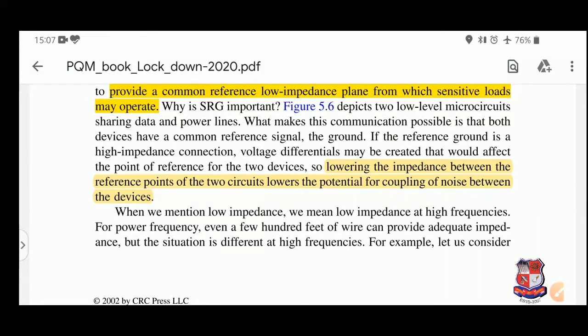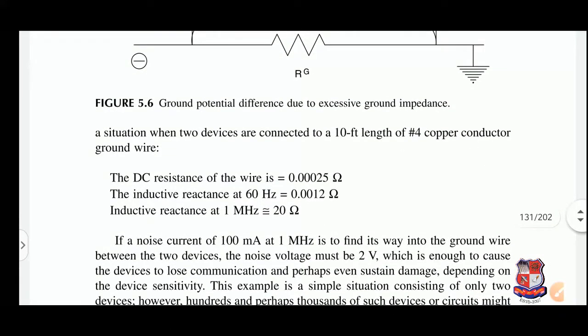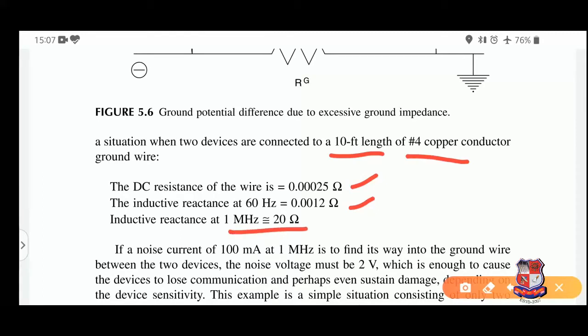When we mention low impedance, we mean low impedance at high frequencies. For power frequency, even a few hundred feet of wire can provide sufficient impedance, but the situation is different at high frequency. Communication operates in the megahertz range. Consider an example: two devices connected by a 10-foot length of four-gauge copper conductor. The inductive reactance at 1 MHz is 20 ohms. With a noise current of 100 milliamperes at 1 MHz, V = I × R gives 100 mA × 20 Ω = 2 volts.